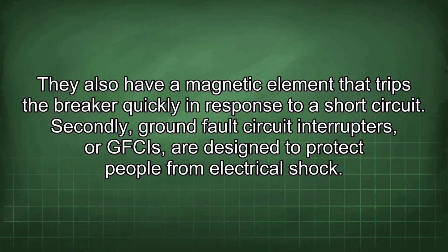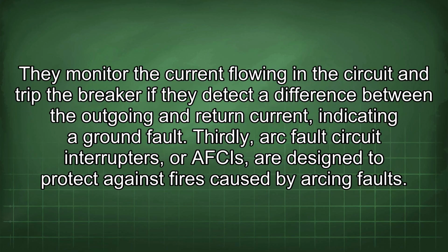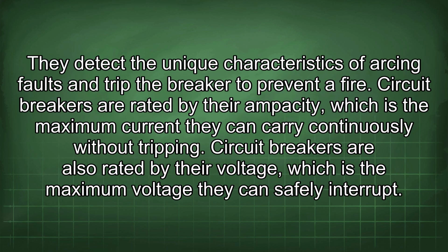Secondly, ground fault circuit interrupters, or GFCIs, are designed to protect people from electrical shock. They monitor the current flowing in the circuit and trip the breaker if they detect a difference between the outgoing and return current, indicating a ground fault. Thirdly, arc fault circuit interrupters, or AFCIs, are designed to protect against fires caused by arcing faults. They detect the unique characteristics of arcing faults and trip the breaker to prevent a fire.